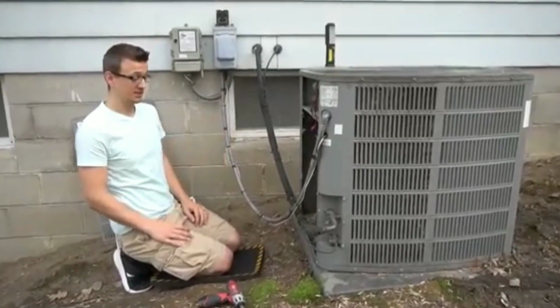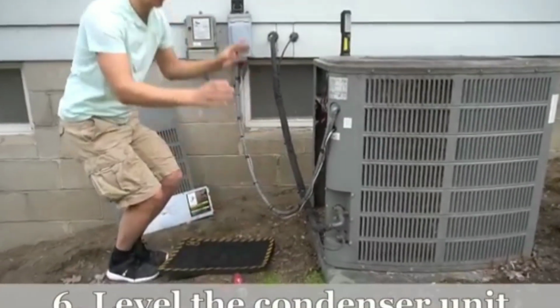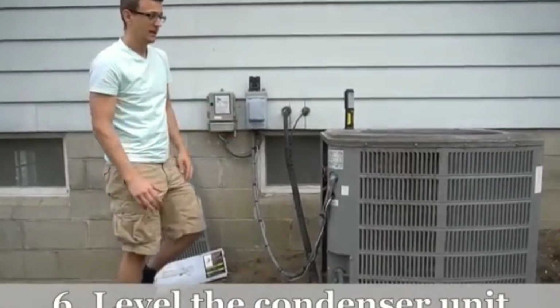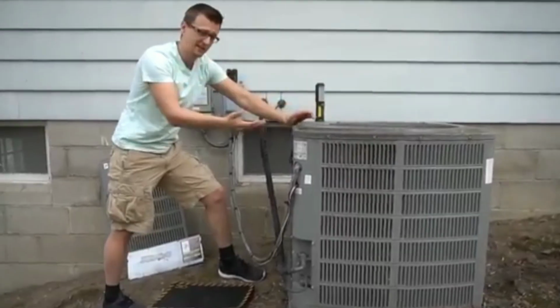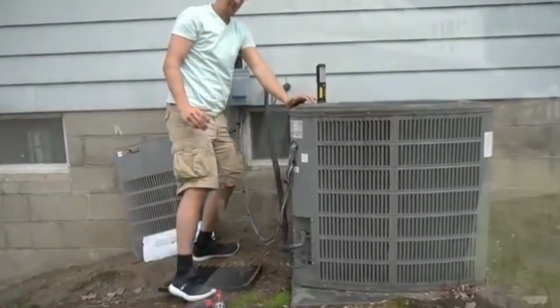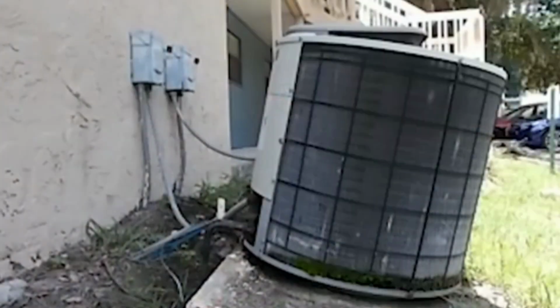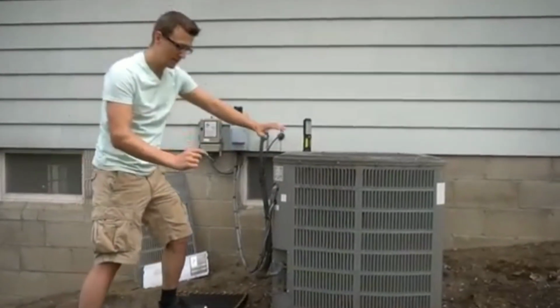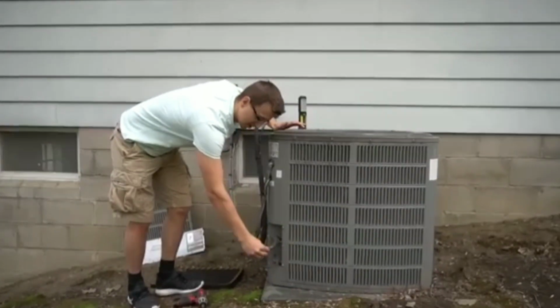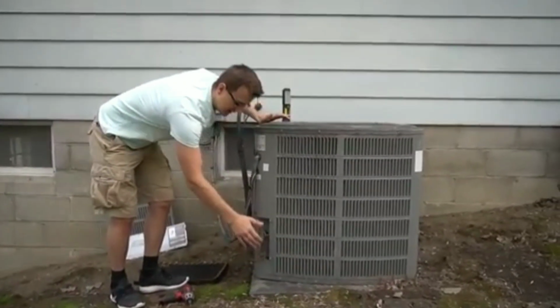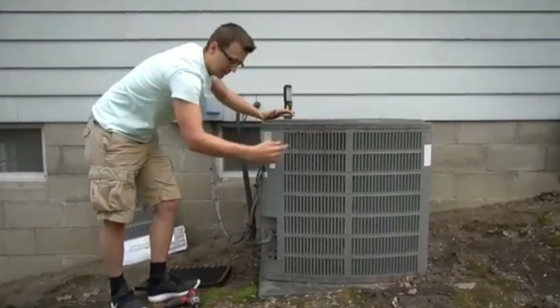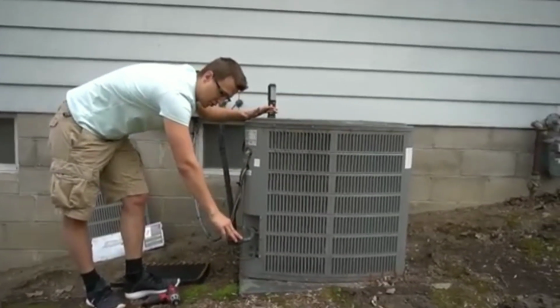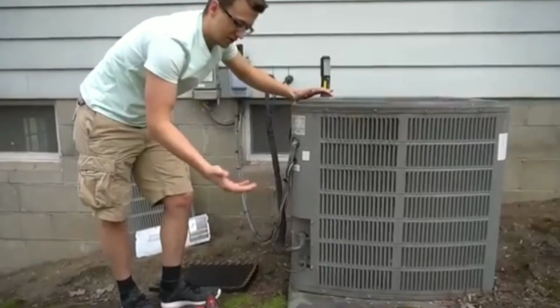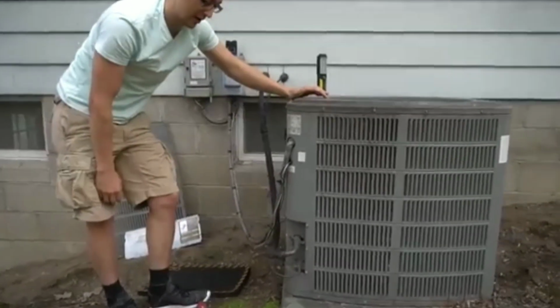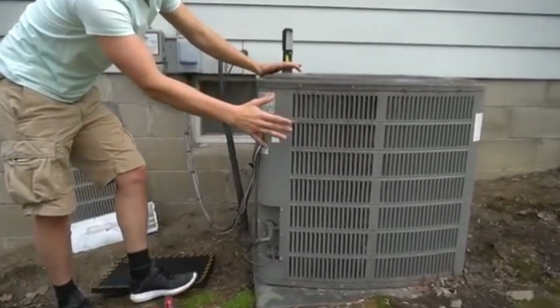And maintenance tip number 6 is to make sure that your AC condenser unit is leveled. If it's just slanted a little bit, that's no big deal, but I see some air conditioners that are really sagging to one side, and actually it's pretty easy to level them. Do keep in mind that you have some copper pipes coming out of your air conditioner unit, so don't move your unit too much, because if for some reason you break a joint or kink a line, then you'll have a Freon leak and that opens a whole new can of worms. But you can move this thing a little bit.